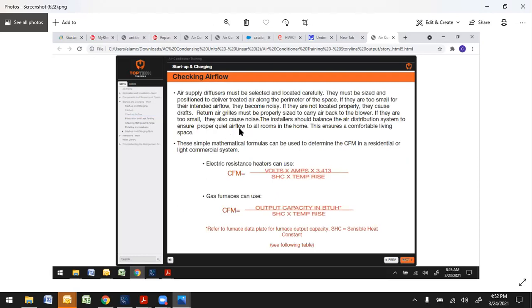So if you want to check airflow, there are some equations down here, but one big thing is air supply diffusers must be selected and located carefully. They must be sized and positioned to deliver treated air along the perimeter of the space. If they are too small for their intended airflow, they will be noisy, they'll whistle. If they are not located properly, they cause drafts.